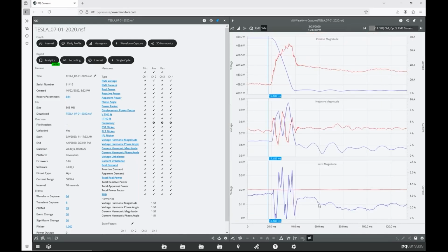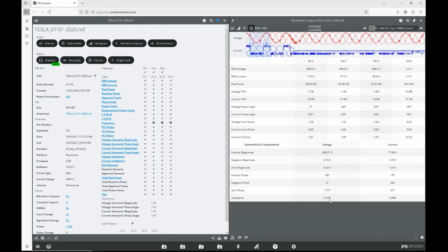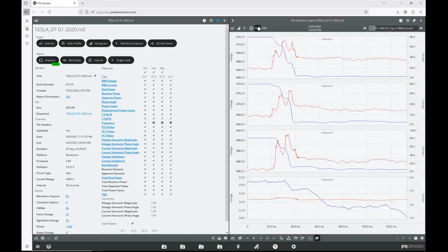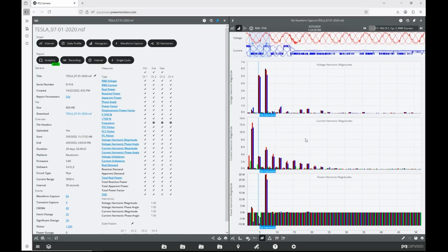We can actually take a look at the voltage imbalance on this waveform. Here we are, it's fairly low. We're just a few tenths of a percent, but that's enough to cause a bit of 3rd harmonic on this load, which is, again, most 3-phase nonlinear loads don't have much 3rd harmonic, but this is enough to produce that. But we see the dominant harmonic for voltage is 5th and 7th, and that is what is most likely to be caused by these EV chargers.